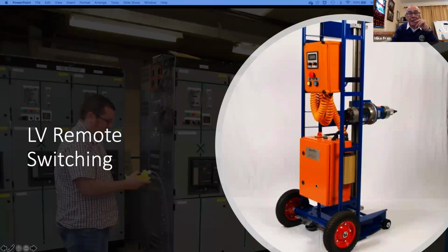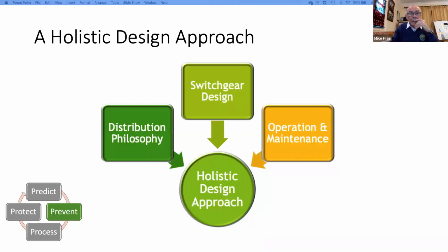On the right-hand side, this is a retrofit, basically. It's a mobile unit that you can rack equipment in and out with. I'm not going to spend too much time on this, but it's another subject area I can speak about for some time.